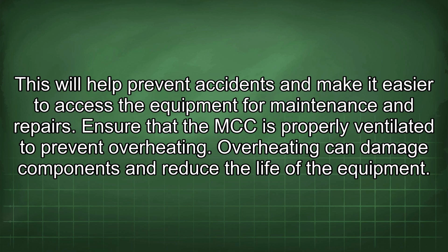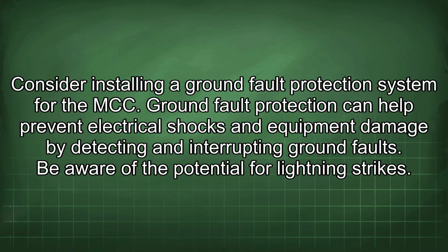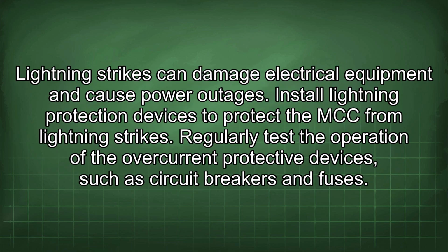Ensure that the MCC is properly ventilated to prevent overheating. Overheating can damage components and reduce the life of the equipment. Consider installing a ground fault protection system for the MCC. Ground fault protection can help prevent electrical shocks and equipment damage by detecting and interrupting ground faults. Be aware of the potential for lightning strikes. Lightning strikes can damage electrical equipment and cause power outages. Install lightning protection devices to protect the MCC from lightning strikes.